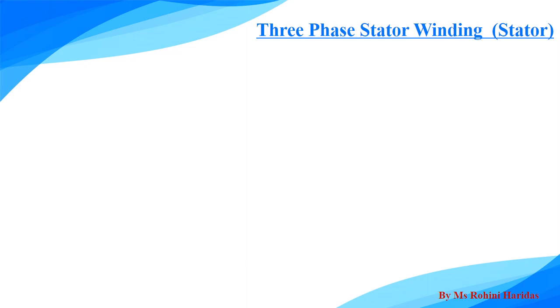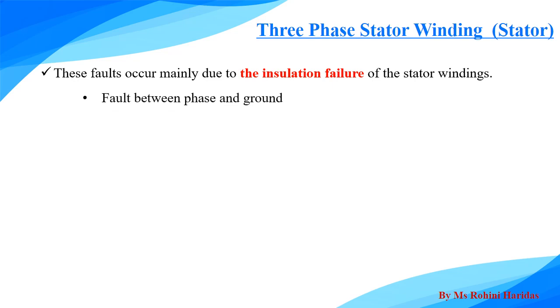That is, three-phase stator winding faults. These faults occur mainly because of the insulation failure of the stator winding. These faults includes faults between the phase and the ground, faults between the phases and interturn faults involving the turns of the same phase winding.